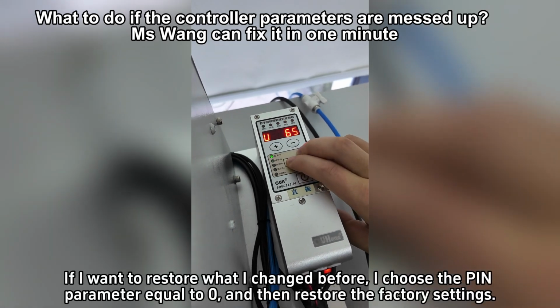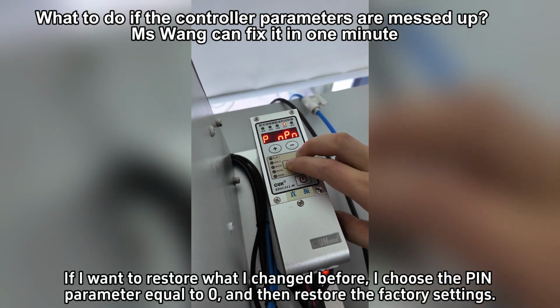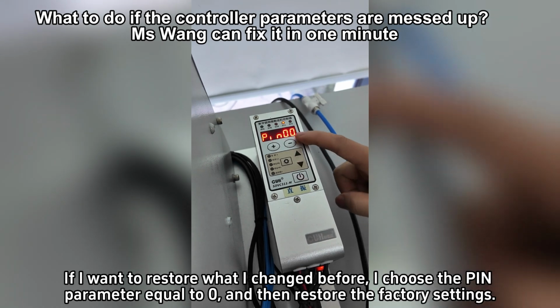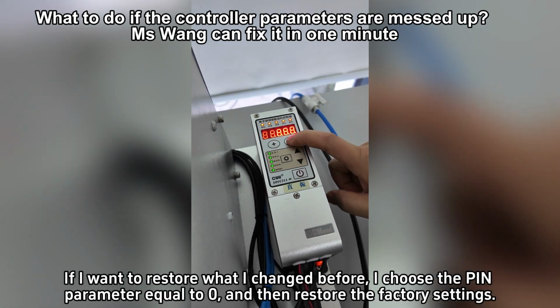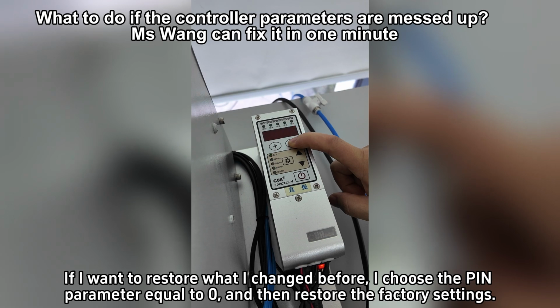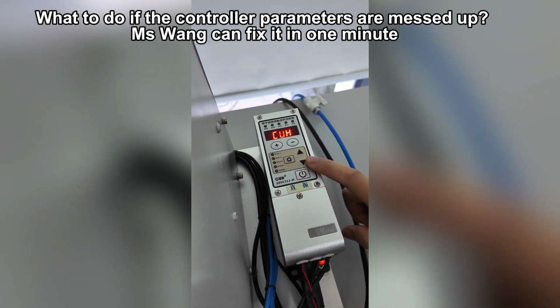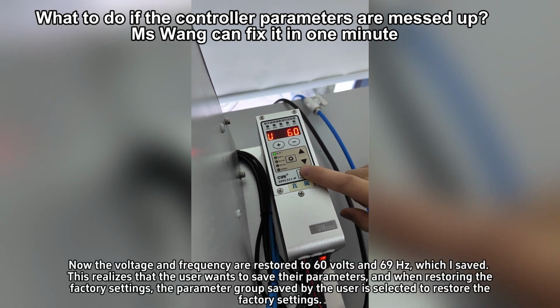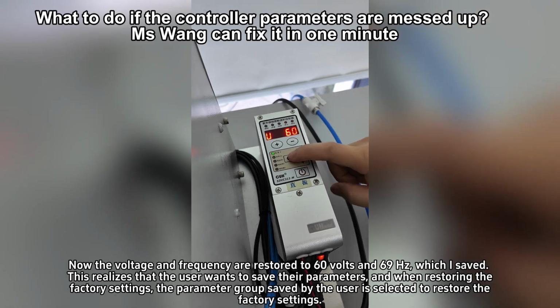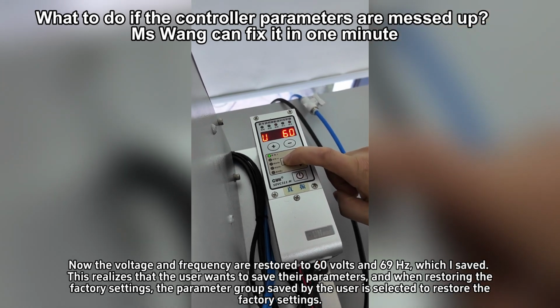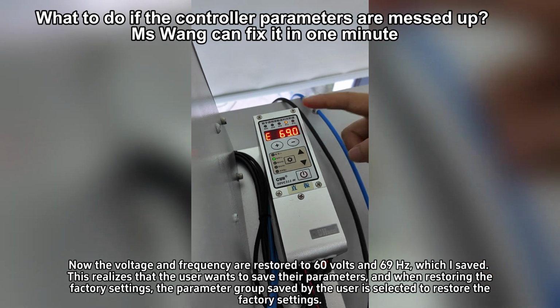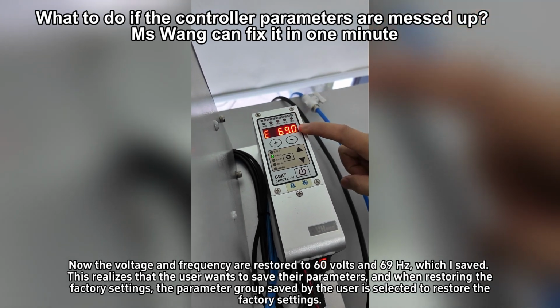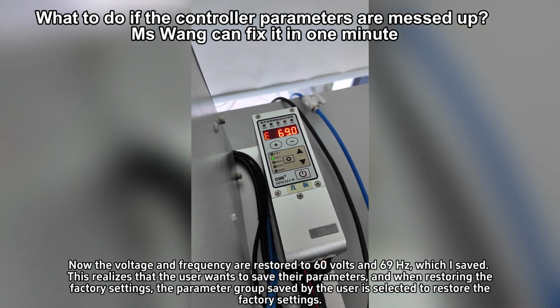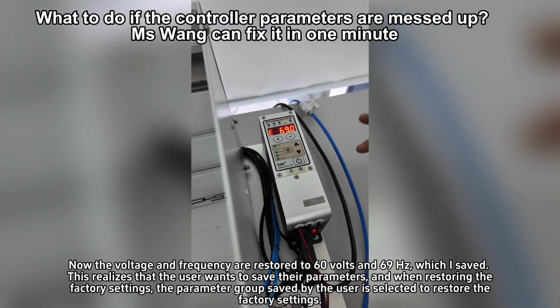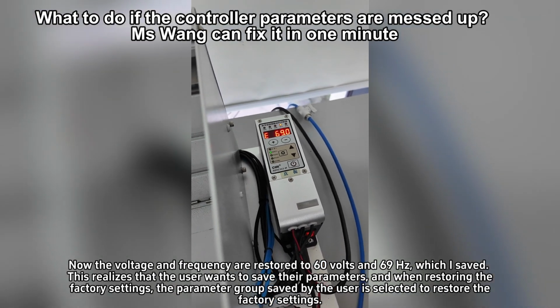If I want to restore what I changed before, I choose the pin parameter equal to 0, and then restore the factory settings. Now the voltage and frequency are restored to 60 volts and 69 Hz, which I saved. This realizes that the user can save their parameters, and when restoring the factory settings, the parameter group saved by the user is selected to restore.